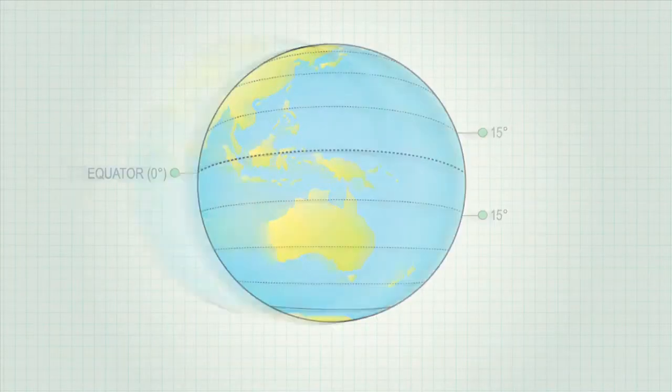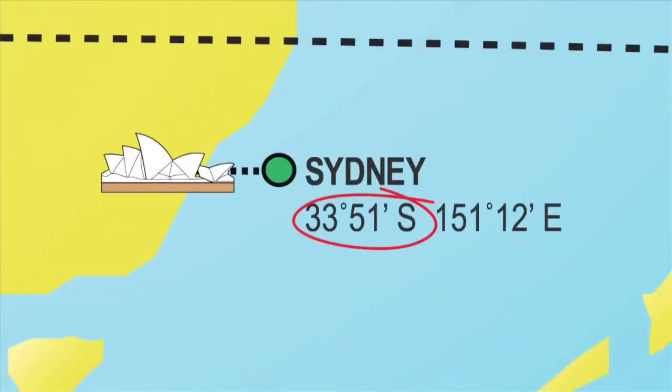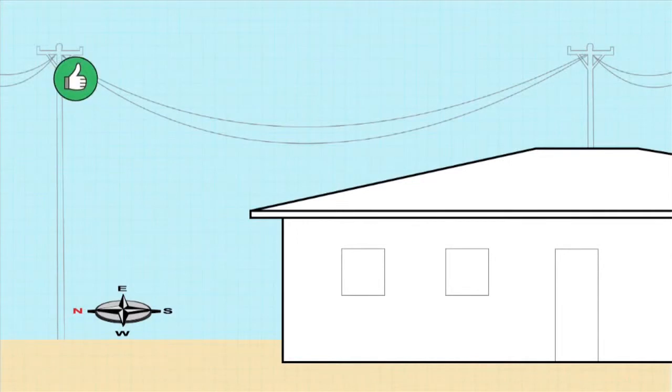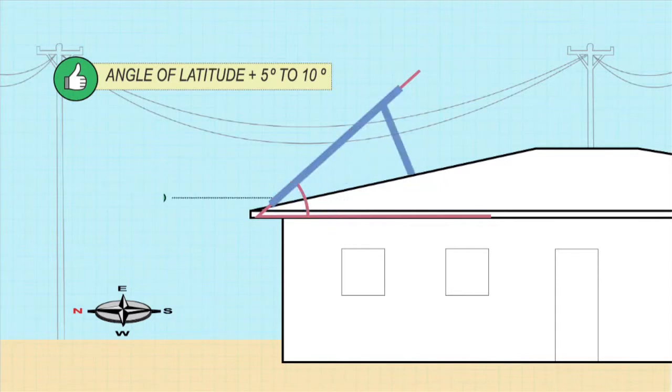The ideal inclination is the angle of latitude plus 5 to 10 degrees. Sydney's latitude is 33.5 degrees, so an ideal angle of inclination would be around 40. However, plus or minus 15 degrees would still provide adequate performance.